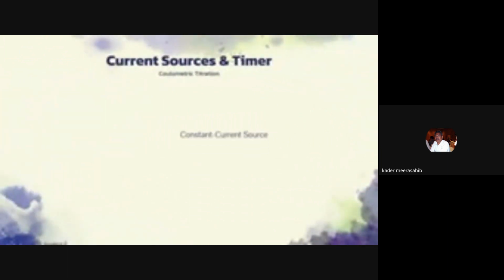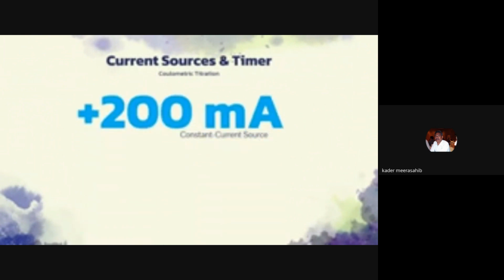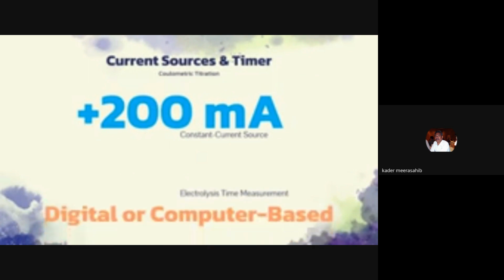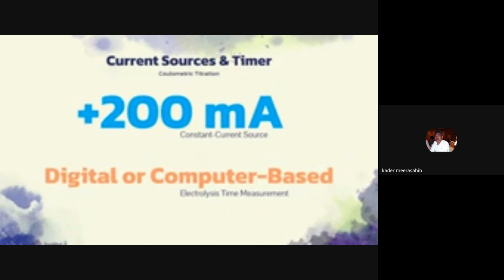The constant current source for a coulometric titration is an electronic device capable of maintaining a current of 200 milliamperes or more that is constant to a few hundredths percent. Such constant current sources are available from several instrument manufacturers. The electrolysis time can be measured very accurately with a digital timer or a computer-based timing system.